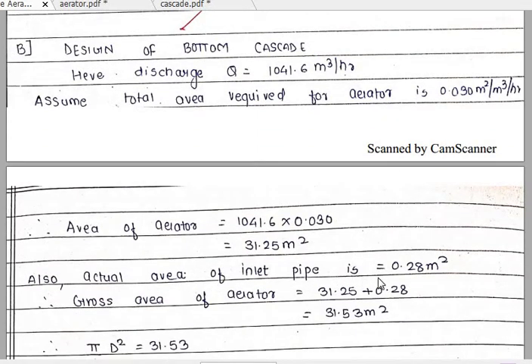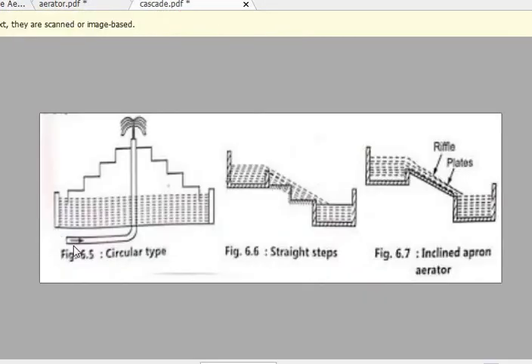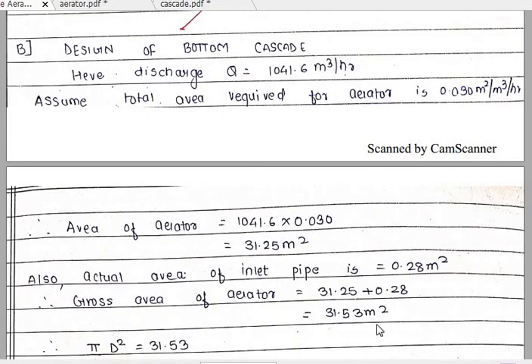The actual area of the inlet pipe is 0.28 meter square. Since the inlet pipe passes through the cascade aerator, the area occupied by the pipe must be added. Therefore the gross area of the aerator equals 31.25 plus 0.28 equals 31.53 meter square. Since it is a circular type aerator, we use pi by 4 into D squared equals 31.53 to calculate the bottom diameter. Solving, D equals 6.35 meter — this is the diameter of the bottom cascade.